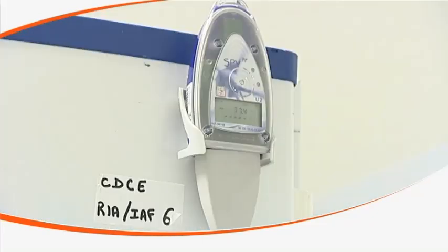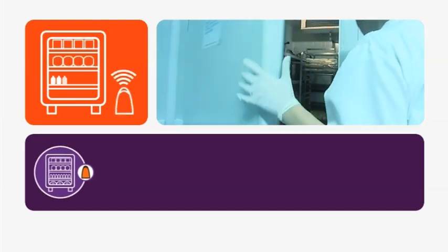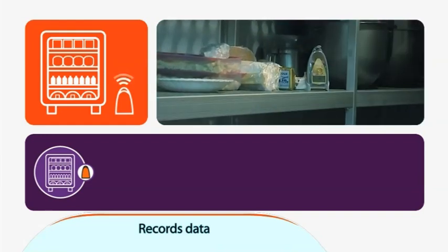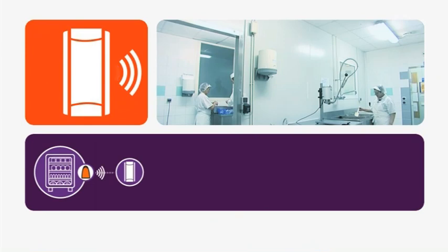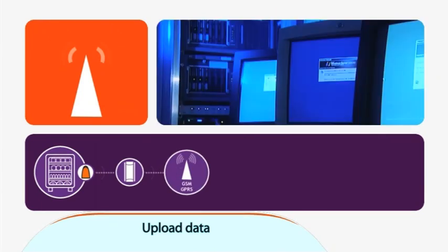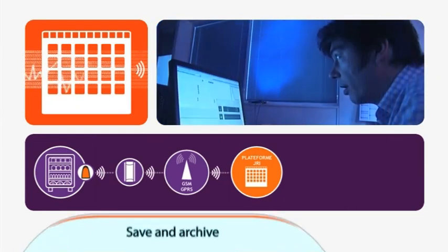The key benefit to this innovative system is that it operates automatically. The SPY-RF wireless data loggers are installed into the equipment that you wish to be monitored. Measurements are then transmitted wirelessly by long-distance radio frequency to the on-site SiriusBox receiver. The SiriusBox automatically sends all data via a GPRS cellular modem to the JRI Maxent central server, where it is archived continuously.